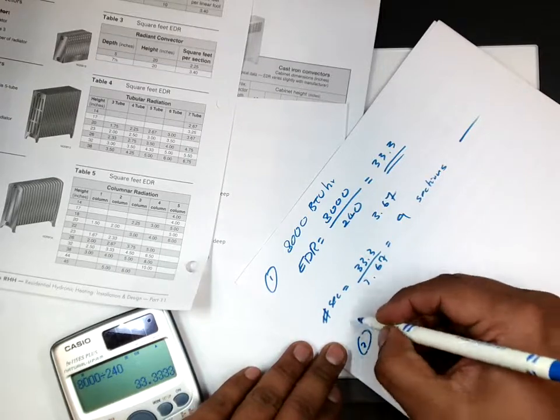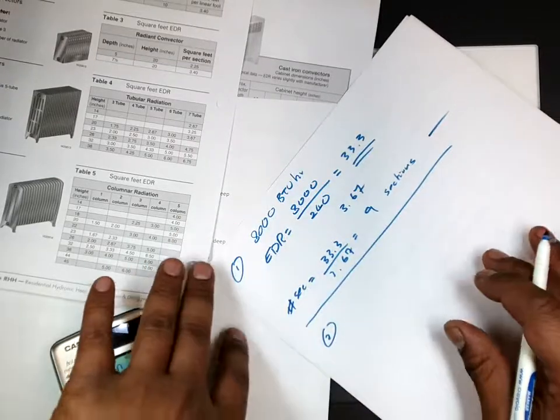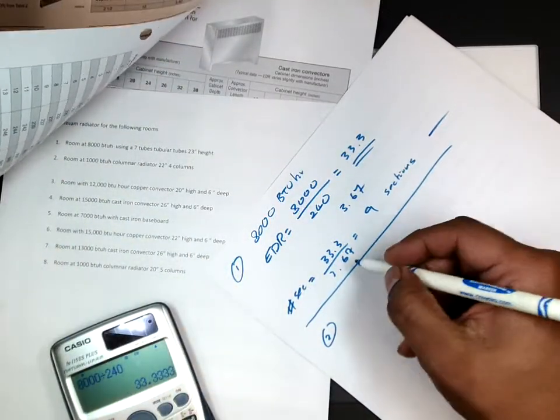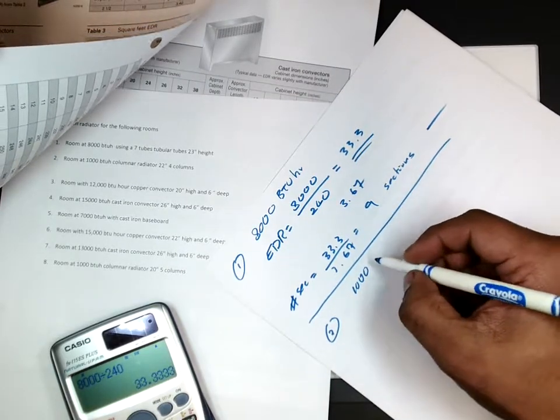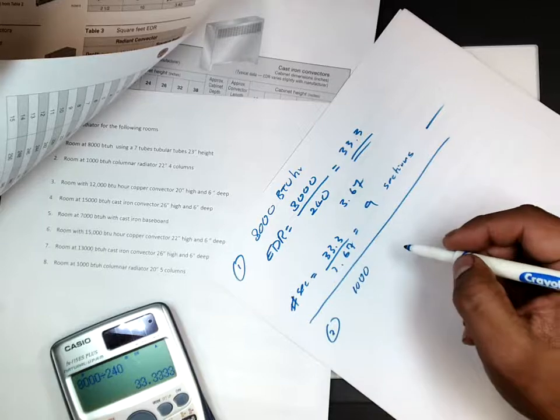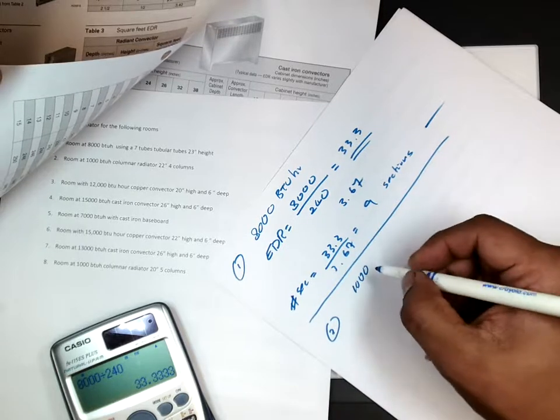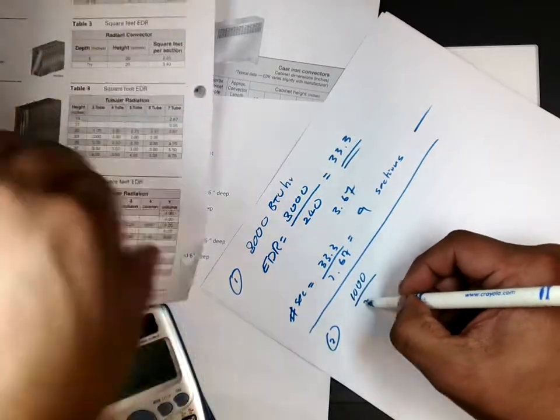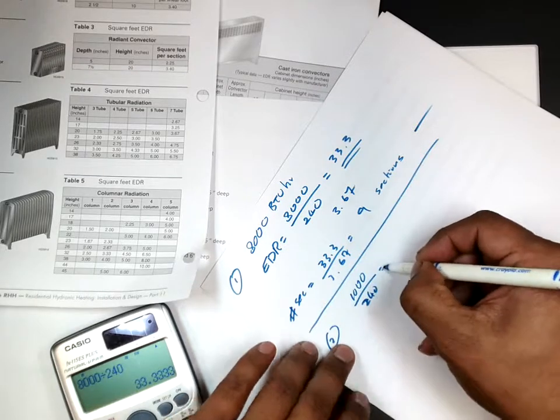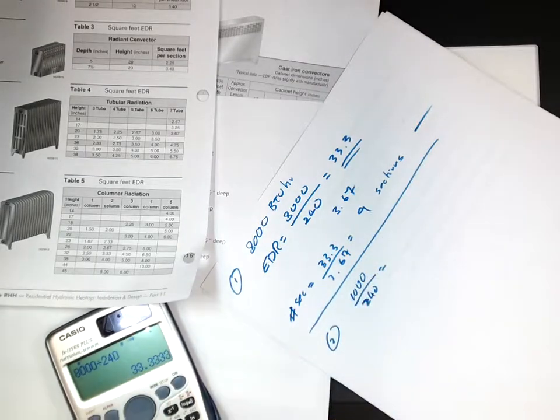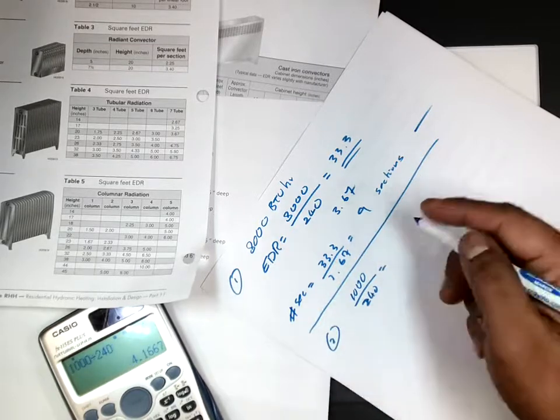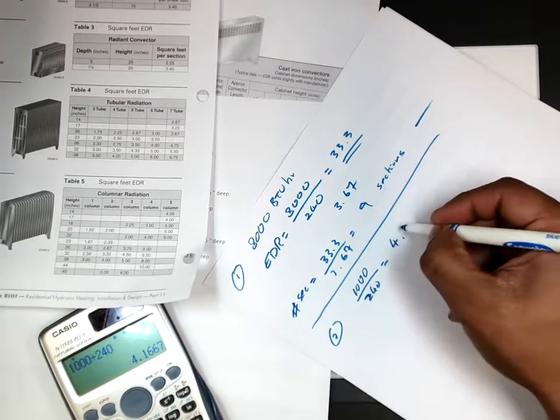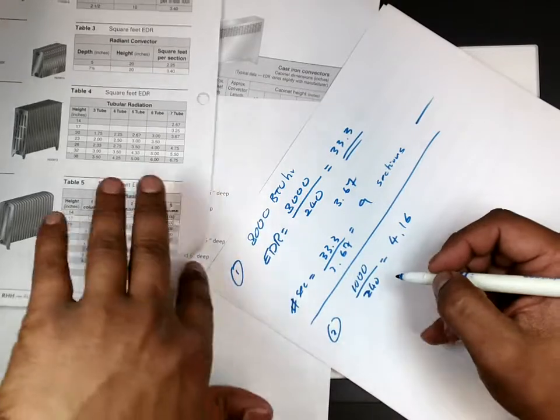Number two. 1,000 BTU. That's very small, probably a bathroom or so. I'm using a columnar radiator. So first I will divide this by 240, so it's going to be really small. 4.16. That's my EDR.